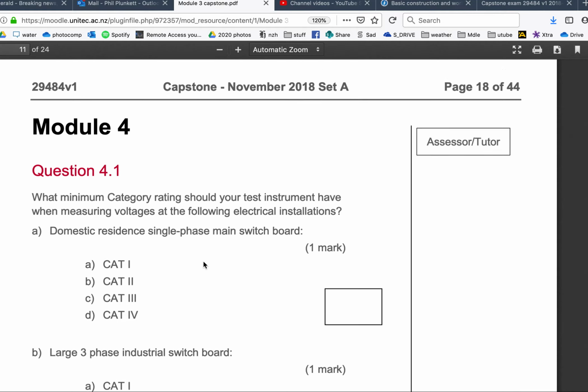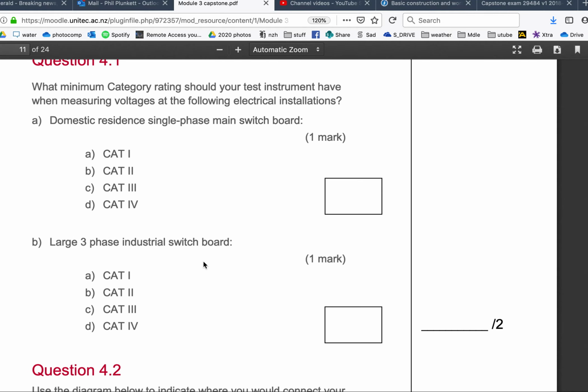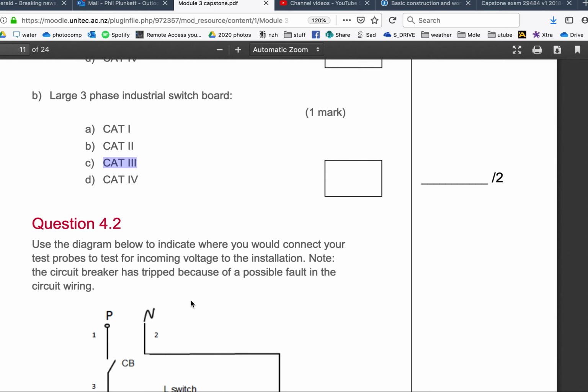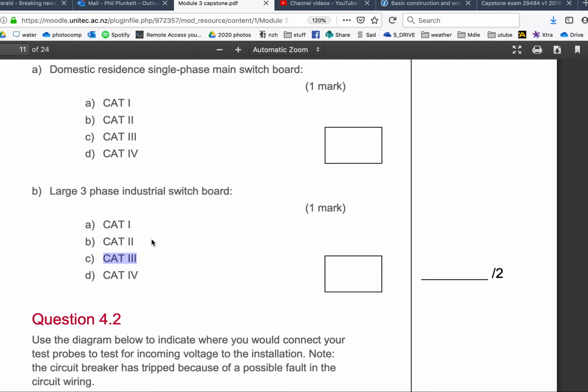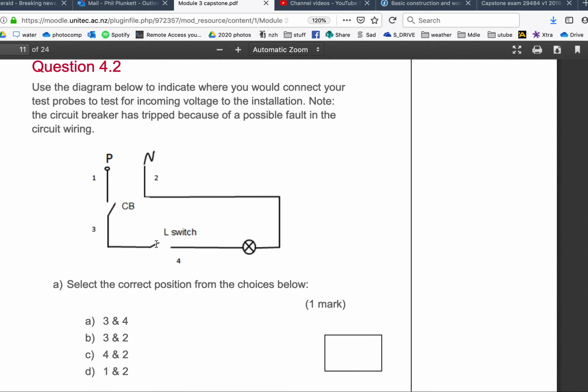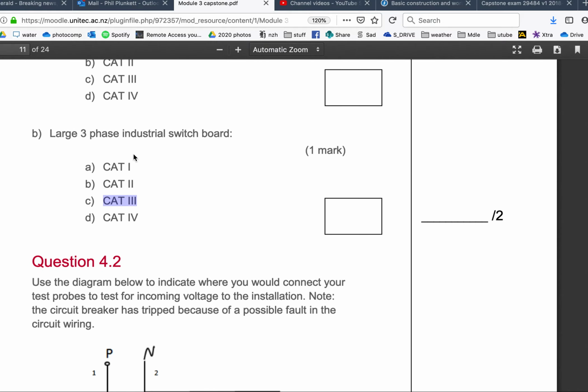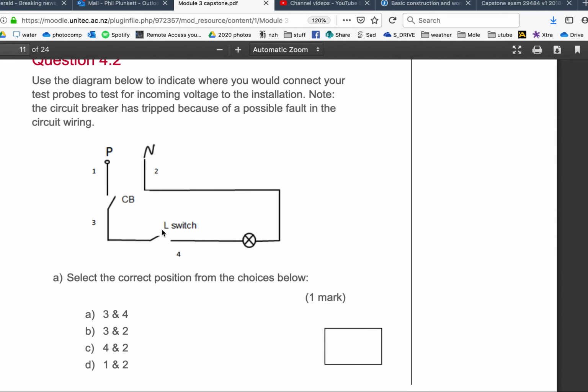Alright, let's scroll down. What minimum category should you have measuring voltages at a single phase at your switchboard? Cat 2, domestic. Cat 3, industrial switchboard, a higher voltage, higher fault currents. If you had a Cat 4 meter, or a Cat 3, you can use it anywhere, right? But that's the minimum.